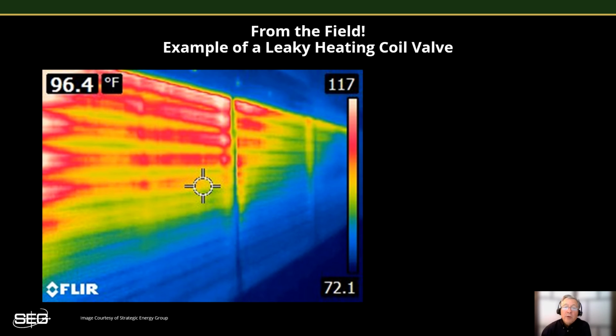This is an infrared picture of a heating coil that has a leaky hot water valve. The white and red colors are the hottest areas, while the color turns yellow to green to blue as the coil gets cooler. With the valve commanded completely shut as it was, we should have seen the coil being mostly blue and uniform in color, meaning no hot water was leaking by.